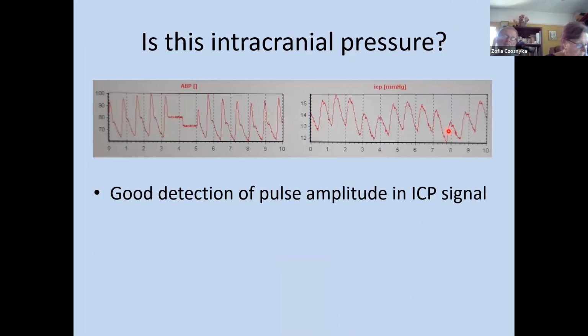An important point. As has already been discussed, the ICP signal has its different pulsatile components. Our method is based on the measurement of intracranial pressure. Therefore, it's essential to confirm that the readings are those of ICP. The detection of pulse amplitude in the signal, as you can see here, nice detection of pulse amplitude, and here also you can see the respiratory component, is critical. If the signal monitored from the valve pre-chamber does not have the pulsatile component, it is a strong indication of blockage of the proximal end.